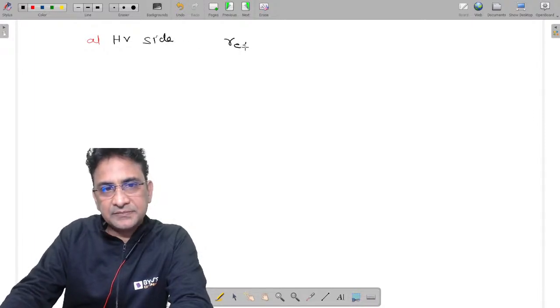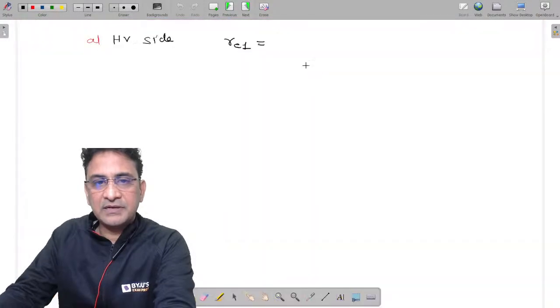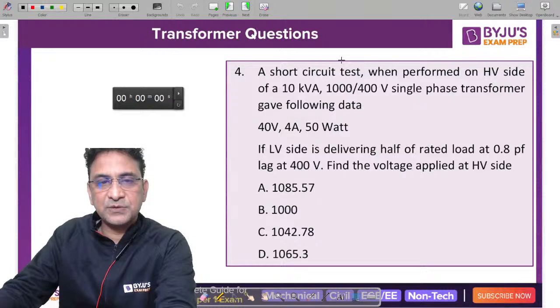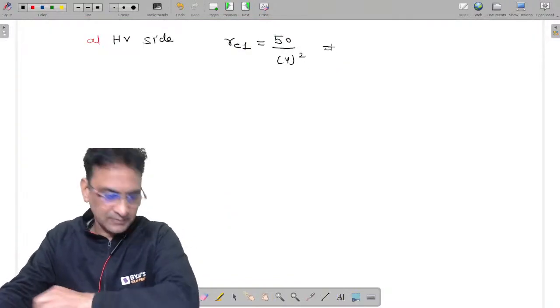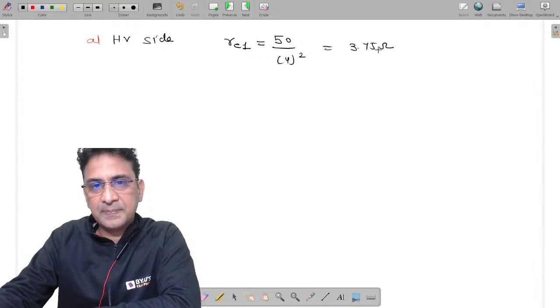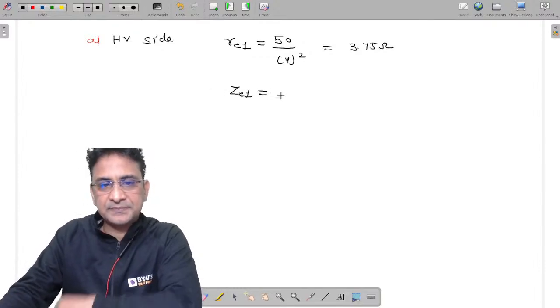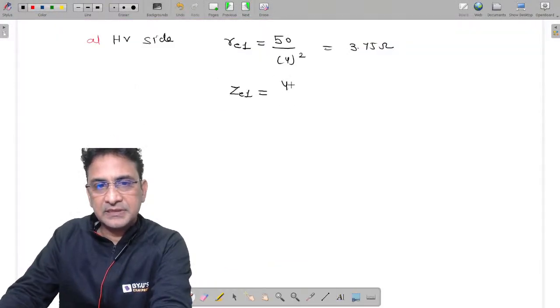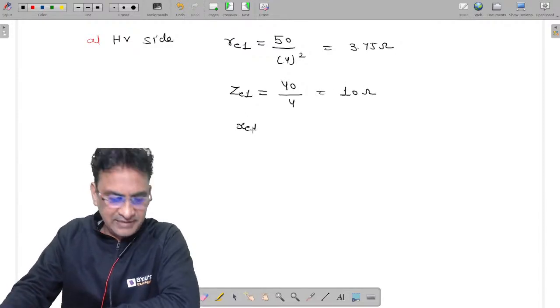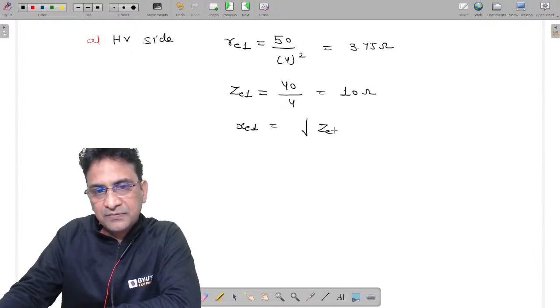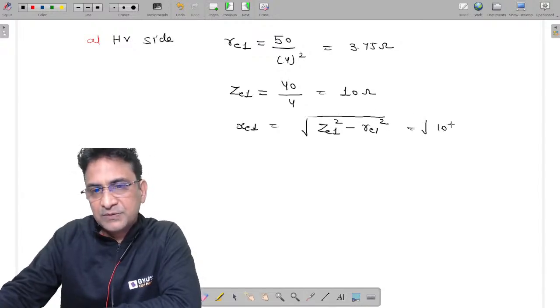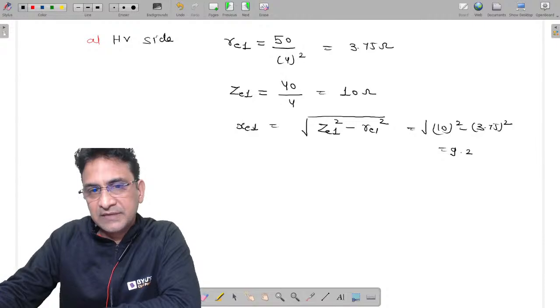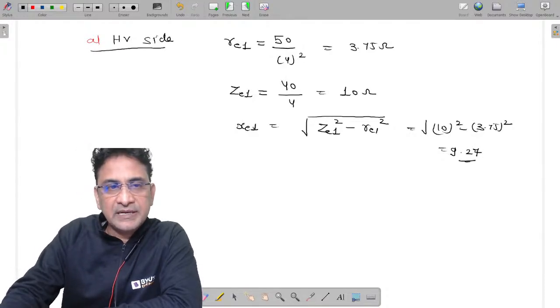What is the equivalent resistance? It will be the wattmeter reading divided by current squared, 4 ampere, since I square R is the power. So it is 3.75 ohm. Equivalent impedance is voltage divided by current, the voltmeter reading divided by the ammeter reading. It is 10 ohm. So you can find the equivalent reactance. It will be the square root of equivalent impedance square minus equivalent resistance square, under root of 10 square minus 3.75 square. We'll get 9.27. That is at the high voltage side. High voltage means the primary side.